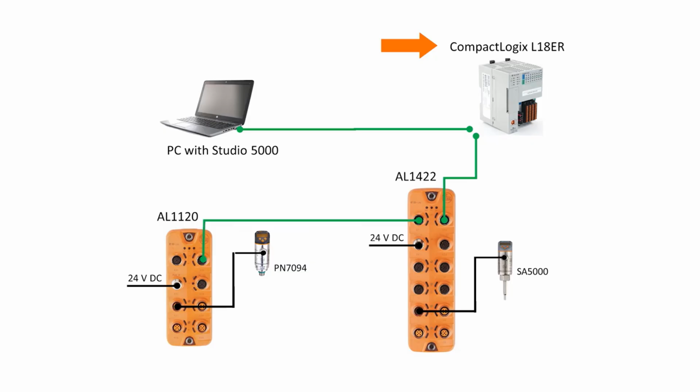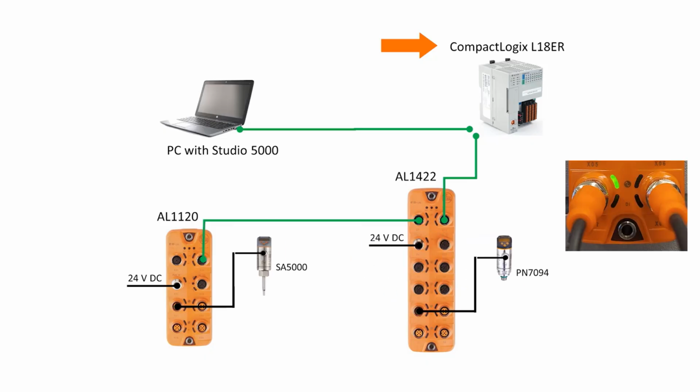If a sensor with the wrong device ID is connected, then the IO-Link LED will blink red on the AL port, and no IO-Link data is transmitted to the PLC. In the manual, this pattern is noted simply as an IO-Link communication error.